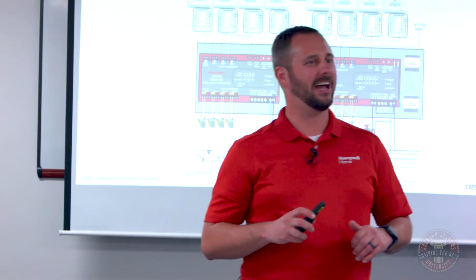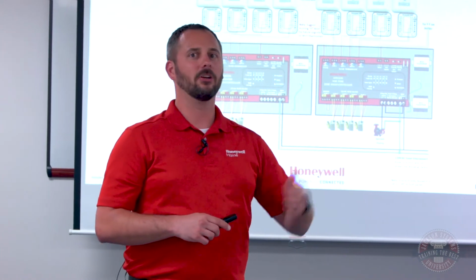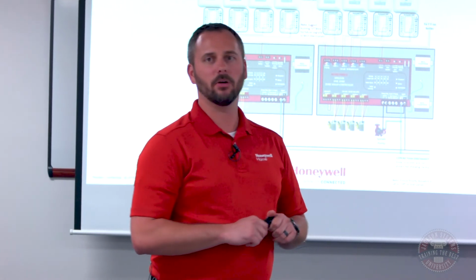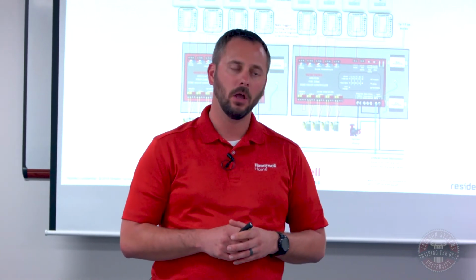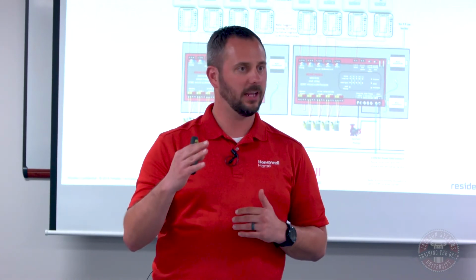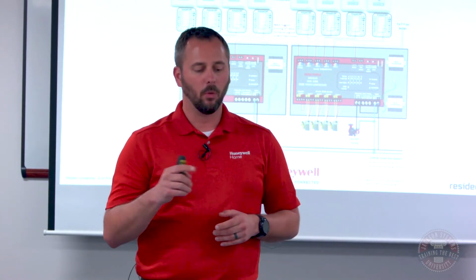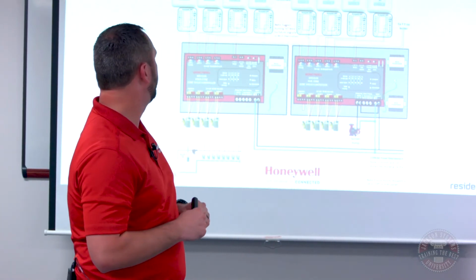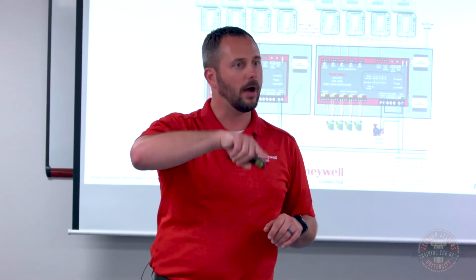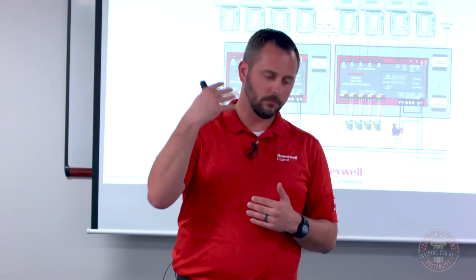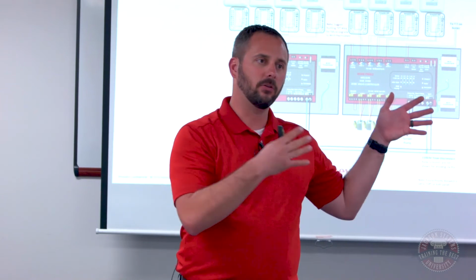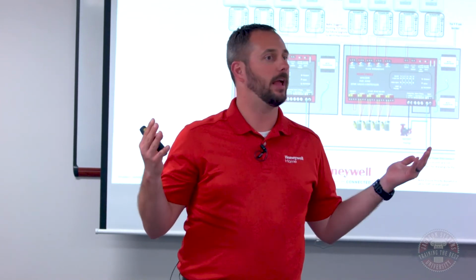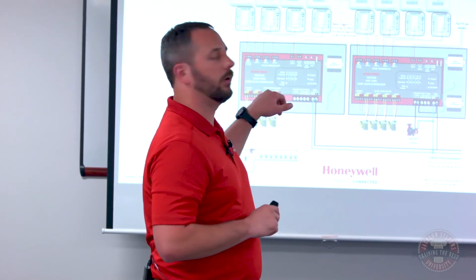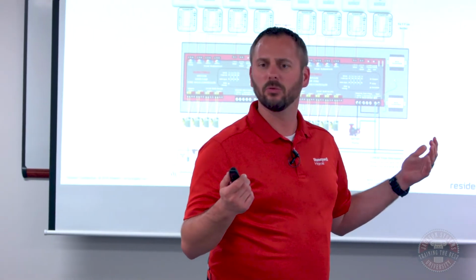So I think it was Constantine that asked the question about expanding the boards. Here's one example of that. So there's different configurations. We actually have a wiring guide available on the internet now that goes through a bunch of different circumstances, and I'll show a couple of those here in just a minute. But what this does is you can basically just take the boiler TT off of, call it the slave board, drop it into the master on any one of the zones, and what that's going to do is sense a call for heat, and the master board basically sees that secondary one as a giant thermostat. So if any one of those thermostats calls for heat, that's what it sees. In order to make that work, because we're not hooking up a zone valve, I never really touched on what an end switch was.